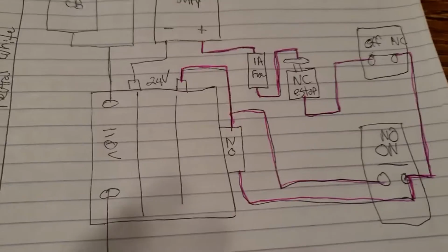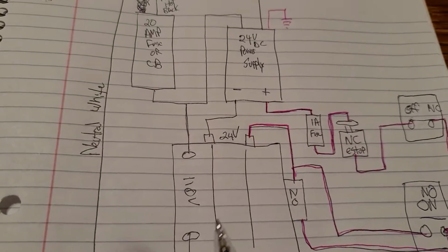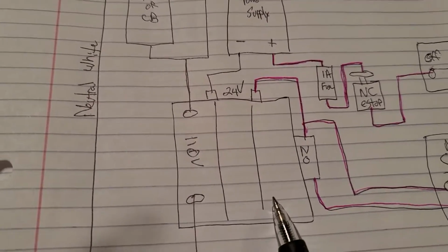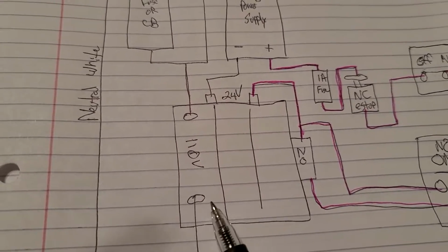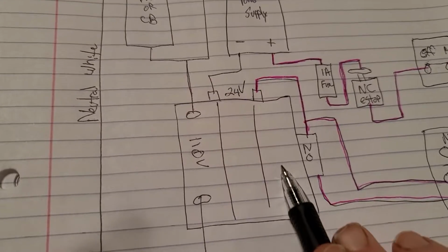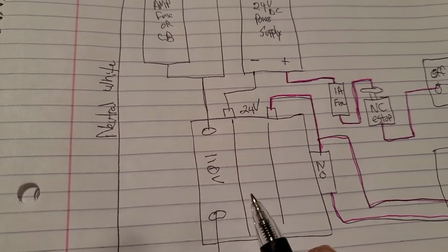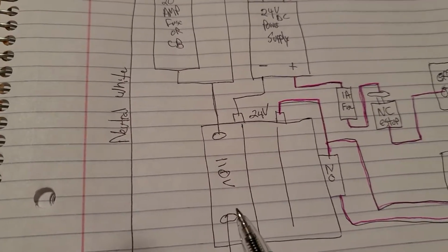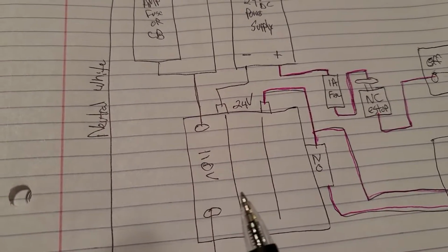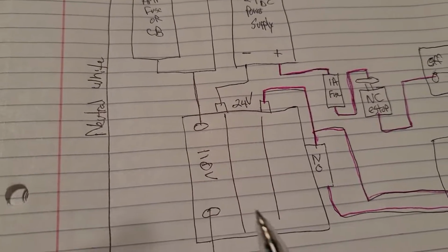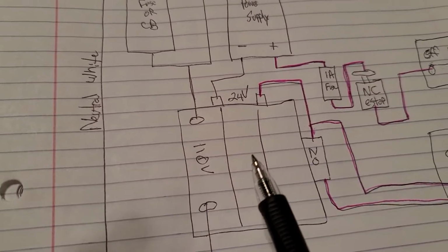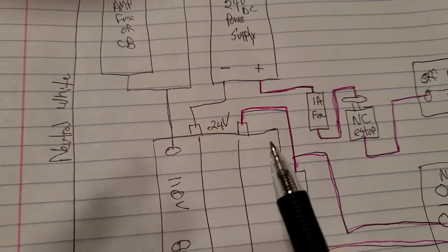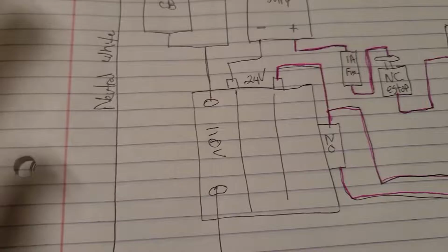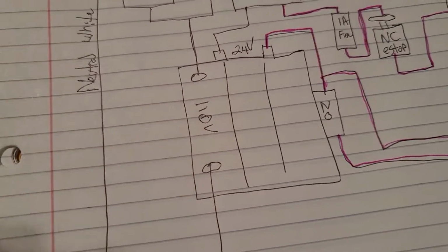And if they don't have that, then it's a matter of just dividing in half. So let's say this was 50 amp rated at 460 volts 3-phase. If it was rated at 230 volts 3-phase, it would be 25 amps. Okay? Now, if it was that, but then you want the single phase rating, you divide in half again. So in this case, 230 volts single phase would be rated at half of that, which would now put us at 12.5. And then if you're going to rate that at 110 volts, you divide in half again. So now you're at like 6 amps. Even though it's originally rated 50, you need to do the math and make sure that it's capable for 110 volts going through it, rated for the amperage you want to run through.